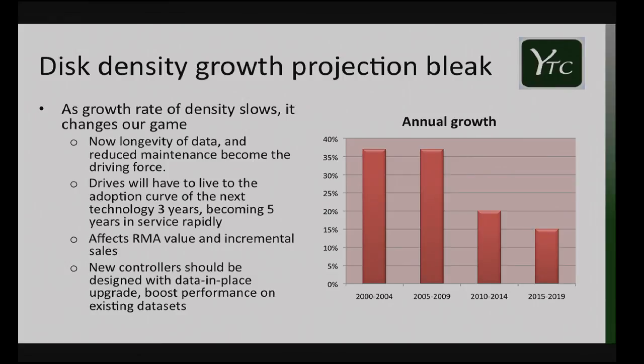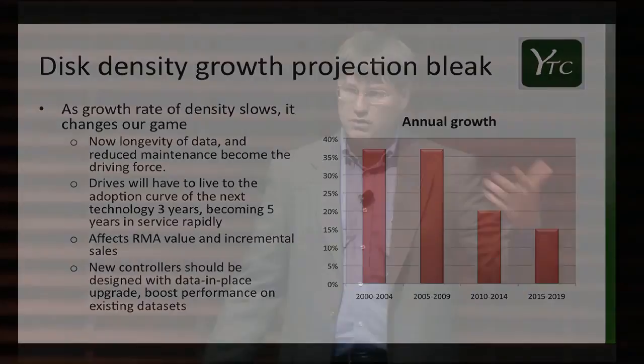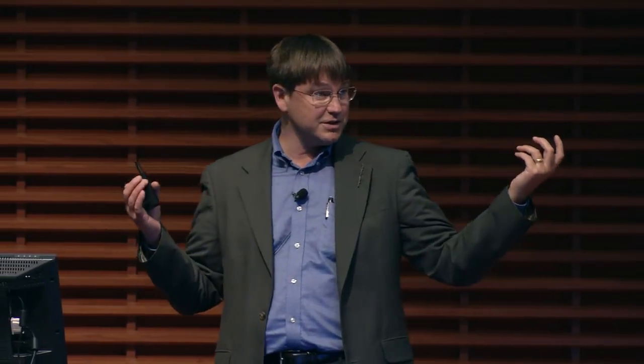So now we're starting to say a 3-year return isn't going to be good enough, it's going to be 5, 7, etc. That's a really interesting problem, and it affects the manufacturers too. Because now we're talking about RMAs coming back, 80% no-trouble-found, because the drive's gone into some weird state you can't fix in the field. You send it back, they put it on their bench, say they don't see a problem, and send it right back to you. This is just lots and lots of churn that nobody needs, and we need to force some fixes to it.